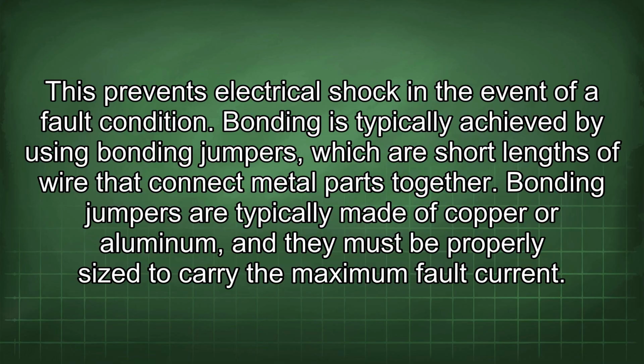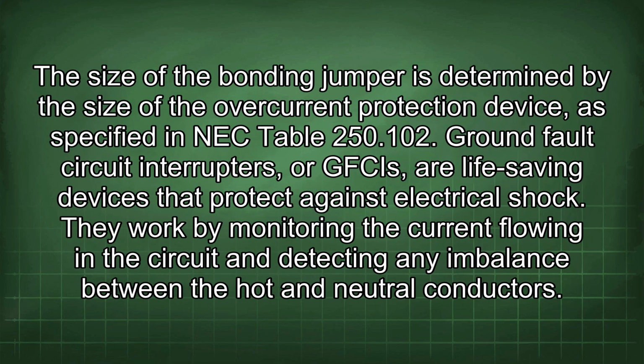Bonding is typically achieved by using bonding jumpers, which are short lengths of wire that connect metal parts together. Bonding jumpers are typically made of copper or aluminum, and they must be properly sized to carry the maximum fault current. The size of the bonding jumper is determined by the size of the overcurrent protection device, as specified in NEC Table 250.102. Ground fault circuit interrupters, or GFCIs, are life-saving devices that protect against electrical shock.